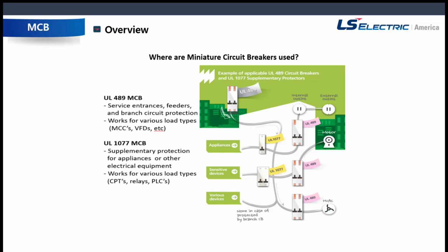So miniature circuit breakers really depend on what type you have. UL 489 are used typically in service entrances or feeders. They've got various load types, including VFDs. UL 1077s also provide supplementary protection for other appliances or electrical equipment. Those are typically used in PLCs or relays or things like that. Also make sure that UL 489 is very typically used in HVAC, we found as well. So just keep an eye on what you're using. If you've got appliances or sensitive devices, UL 1077 is definitely where you want to go. Typically, we see UL 489, but there are plenty of use cases for UL 1077 as well.